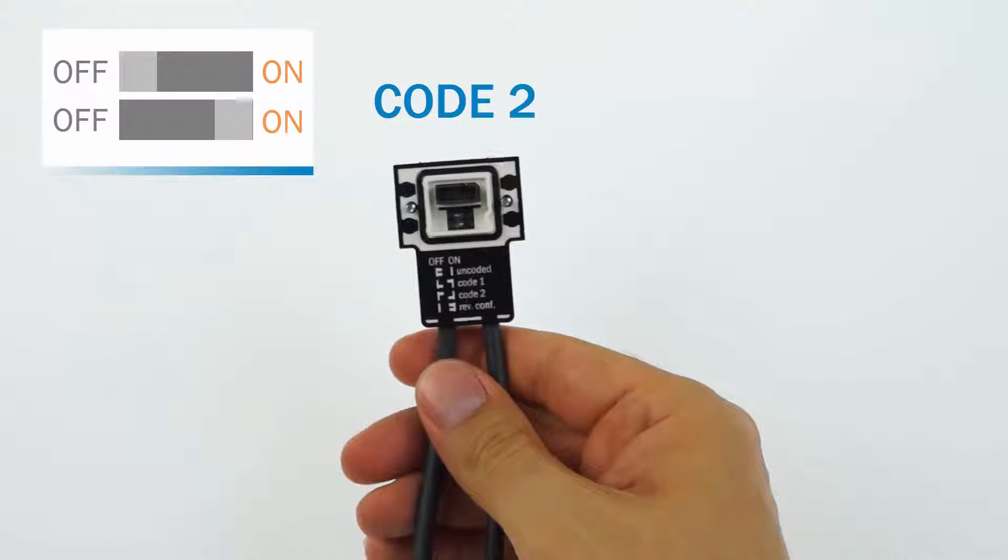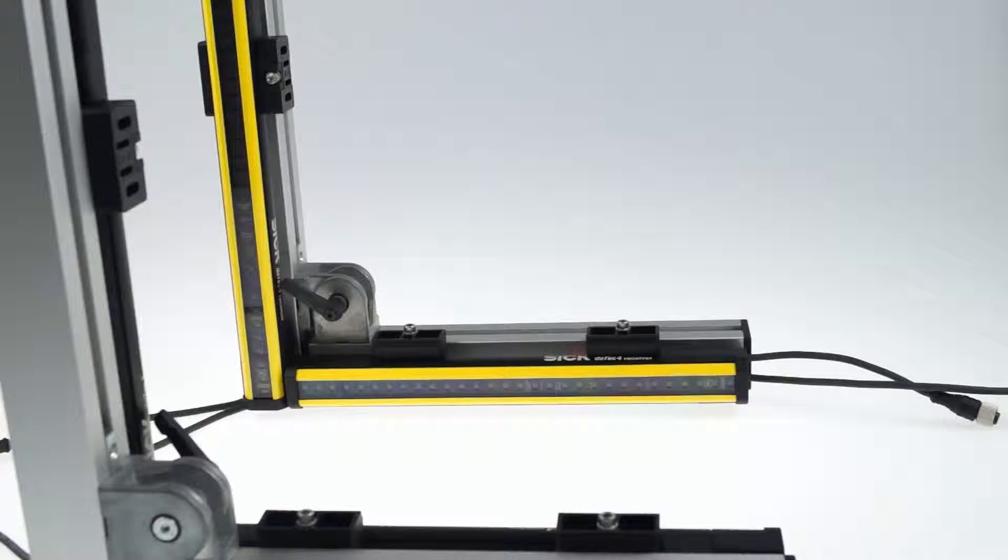Make sure to code all corresponding devices accordingly. If beam coding is configured the field LEDs flash once yellow for code 1 and twice yellow for code 2 each time the system starts up.